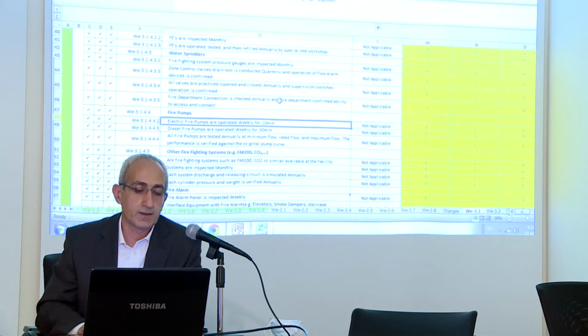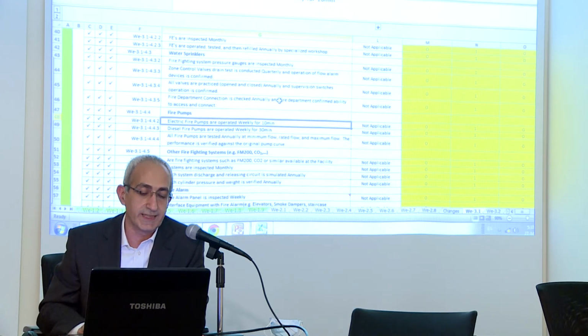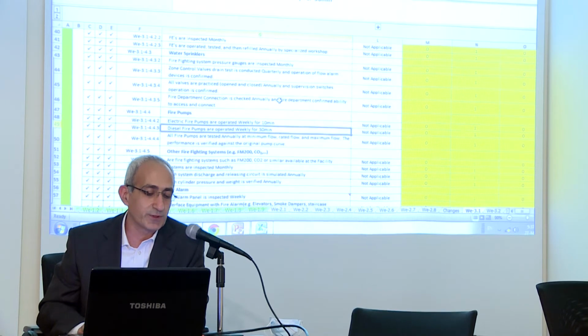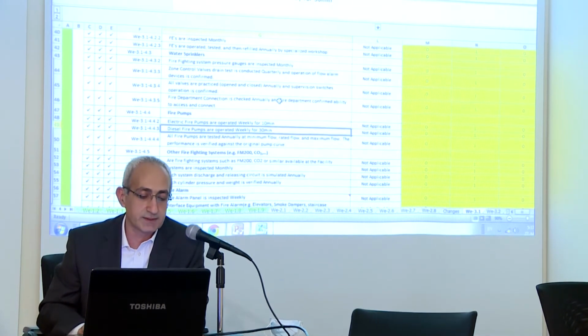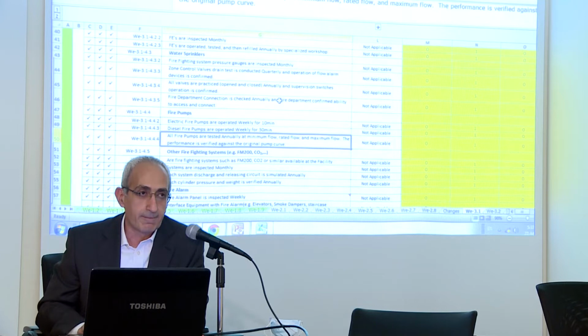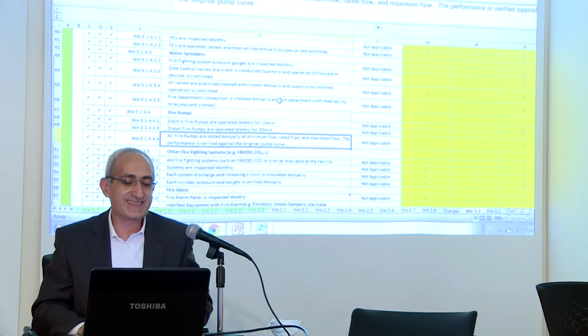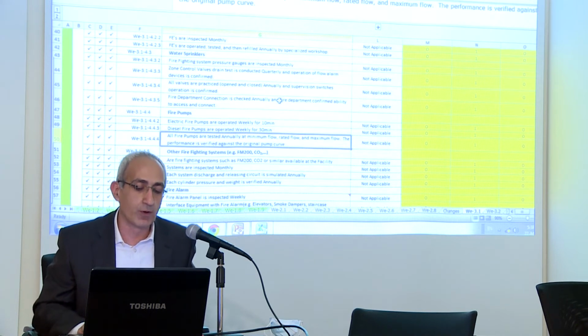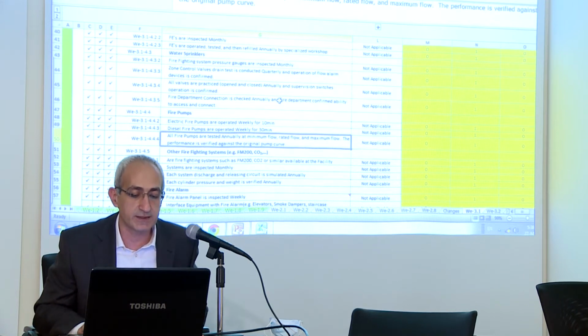Fire pumps, so electrical pumps are operated weekly. We rarely see this guideline committed to. Diesel fire pumps are operated weekly for 30 minutes. All fire pumps are tested annually at minimum flow, rated flow and maximum flow, and the performance is verified against the original pump curve. This is an NFPA 20 requirement. We usually install the pump and forget about it.